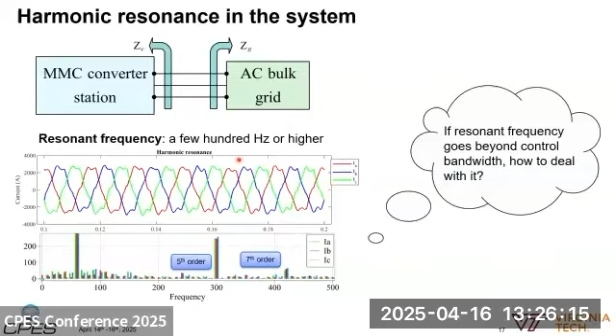The waveform here shows the fifth order and seventh order harmonics as the dominant harmonics components in the system. However, in a real-world system this might not be the case, because the harmonics resonance can be a few hundred hertz or even higher, for example around 1 kilohertz. So if the resonant frequency goes beyond the control bandwidth, how do we deal with it?